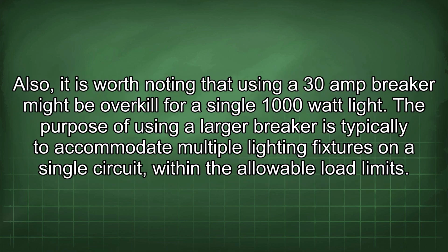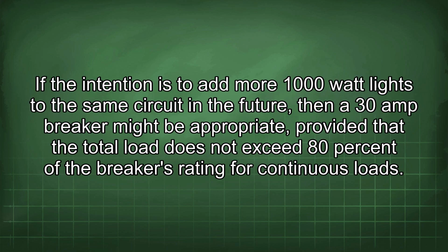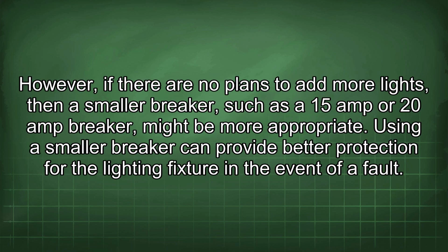Also, it is worth noting that using a 30-amp breaker might be overkill for a single 1000-watt light. The purpose of using a larger breaker is typically to accommodate multiple lighting fixtures on a single circuit within the allowable load limits. If the intention is to add more 1000-watt lights to the same circuit in the future, then a 30-amp breaker might be appropriate, provided that the total load does not exceed 80% of the breaker's rating for continuous loads. However, if there are no plans to add more lights, then a smaller breaker, such as a 15-amp or 20-amp breaker, might be more appropriate.